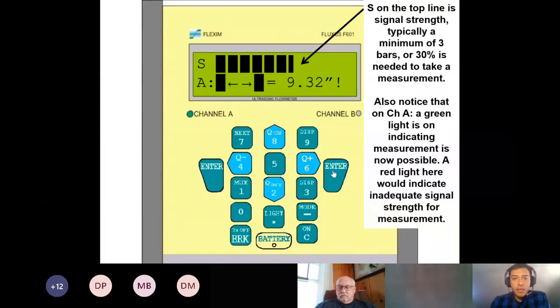The next menu is for your signal strength. Typically, we need about 3 bars of signal for you to get an accurate reading. That's 30%. This here we have more than enough. And you need to make sure you have a green light. The green light's indicating that there's proper communication between the transducers and you're ready to start measuring.